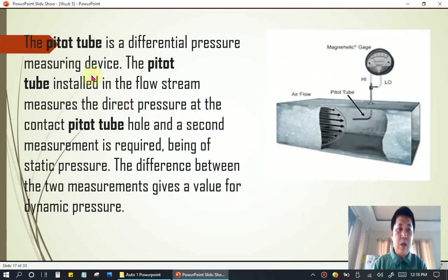Next, we have here the pitot tube. It's a differential pressure measuring device. The pitot tube installed in the flow stream measures the direct pressure at the contact pitot tube hole. A second measurement is required, being the static pressure. The difference between the two measurements gives a value for dynamic pressure. So this is your dynamic pressure here.